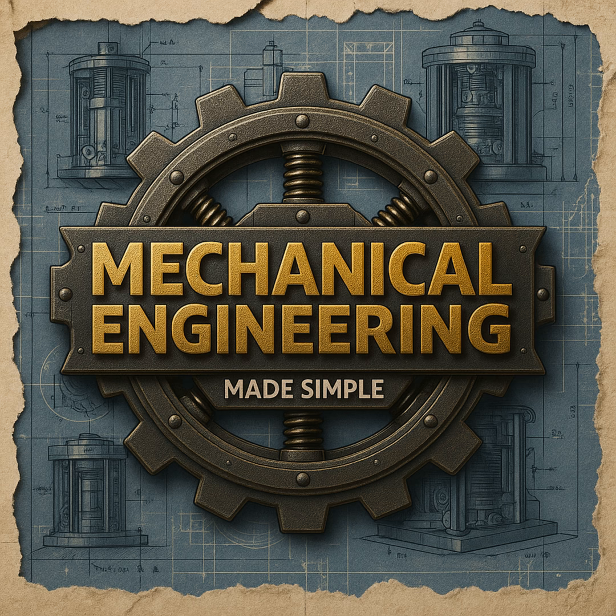This is where the VAV magic happens. Let's talk fan laws. These are fundamental, right? Absolutely fundamental. These govern how fans behave when you change their speed. There are three main laws that are incredibly useful. One, capacity, the volume of air moved. Your CFM, or cubic meters per second, is directly proportional to the fan speed.